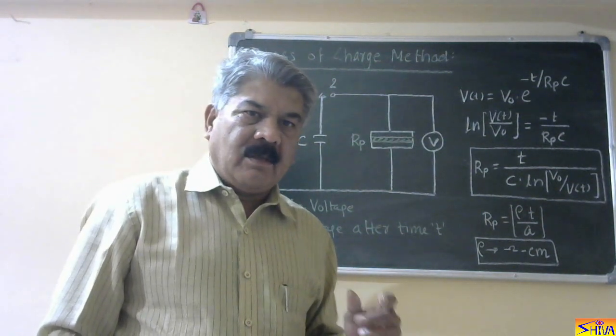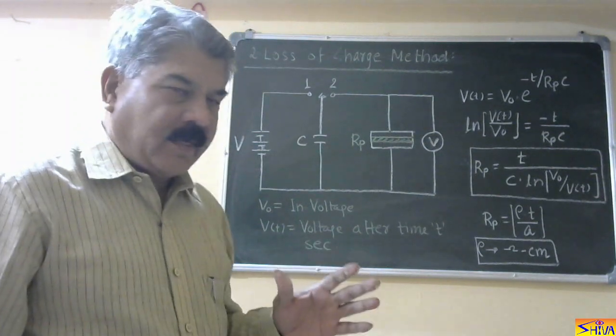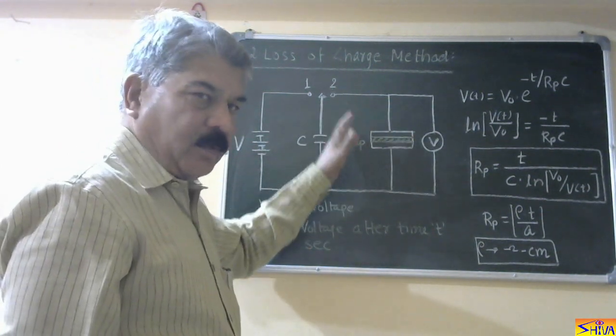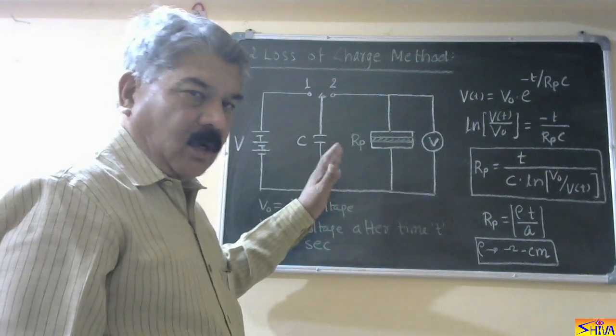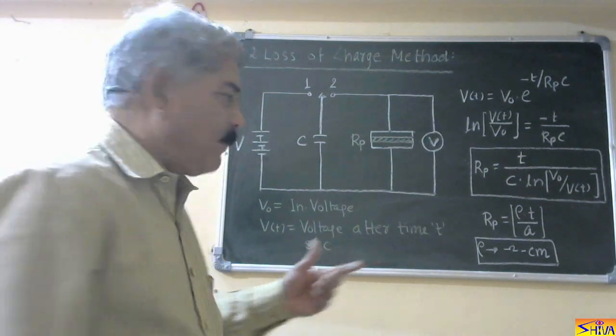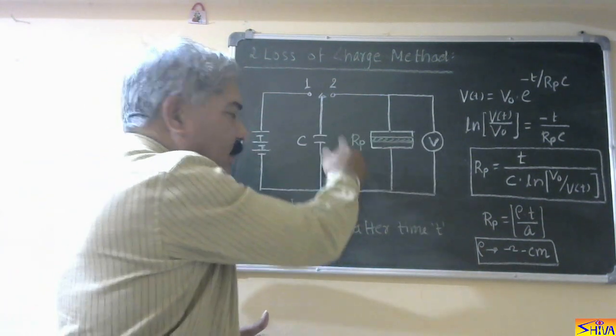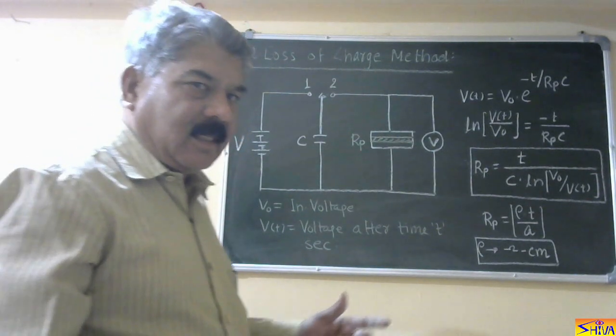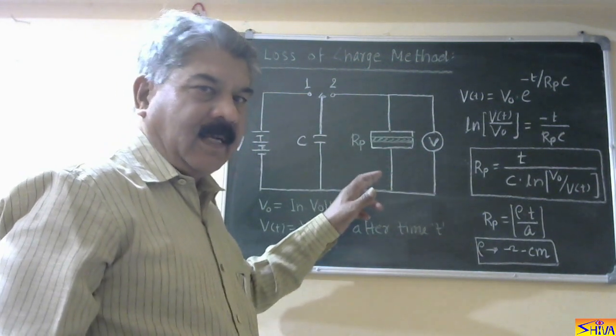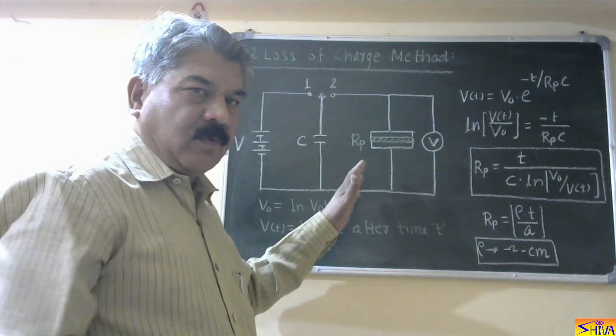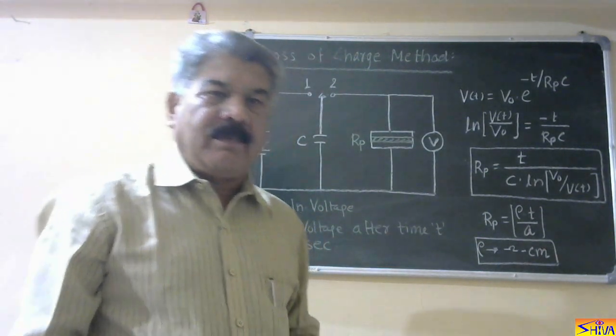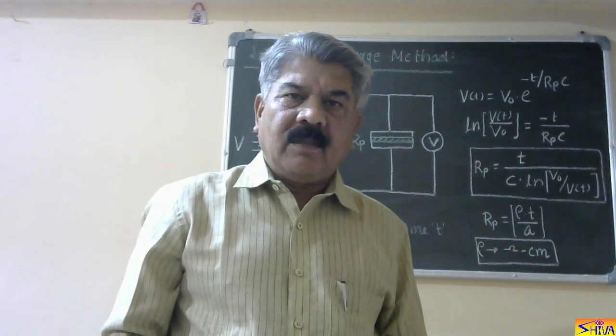However, in this method there is a source of error, because the capacitor also has its own resistance, which we are not accounting for. That capacitor resistance comes in parallel with the test specimen resistance. So the insulation resistance we obtain is actually the parallel combination of these two resistances, introducing some error in the measurement when using the loss of charge method. These are the two methods for measuring the insulation resistance or DC resistivity of the insulation.